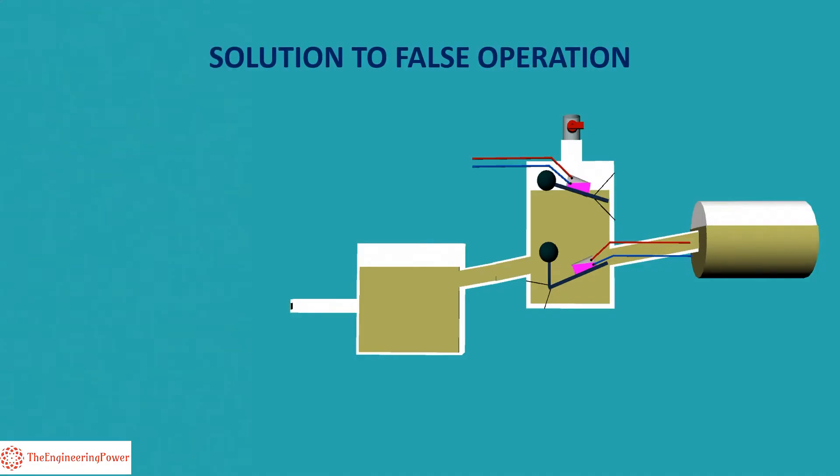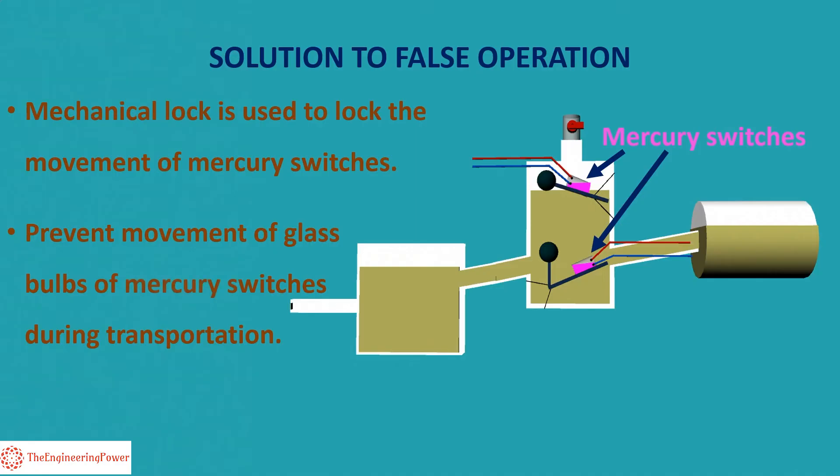The solution to this problem is that mechanical lock is used to lock the movement of mercury switches when oil is being added to a transformer to protect false operation of Buchholz relay resulting in alarm. Mechanical lock is also useful in preventing unnecessary movement of glass bulbs of mercury switches during transportation of Buchholz relays, hence resulting in preventing any damage to mercury switches.